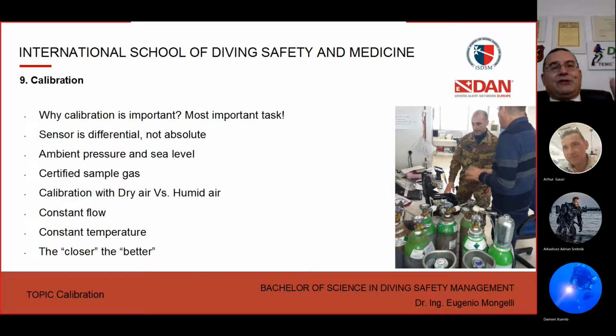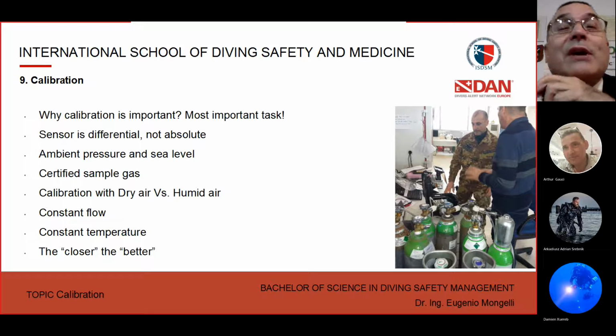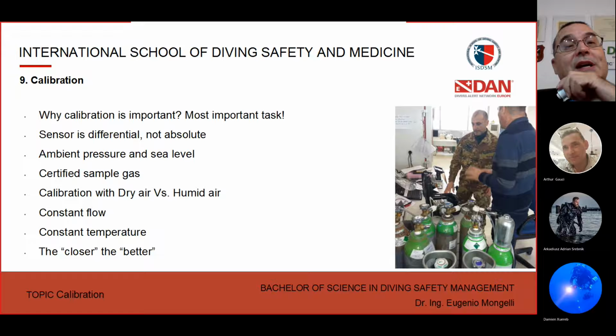So if you are inside a hyperbaric chamber, you know that there is air. This is the sample gas. And you are sure that you are at air, 2 bar, you can do the calibration at 21. And then at the same pressure, if you increase oxygen, the analyzer will read the real concentration, because now you are at constant pressure. Understand?